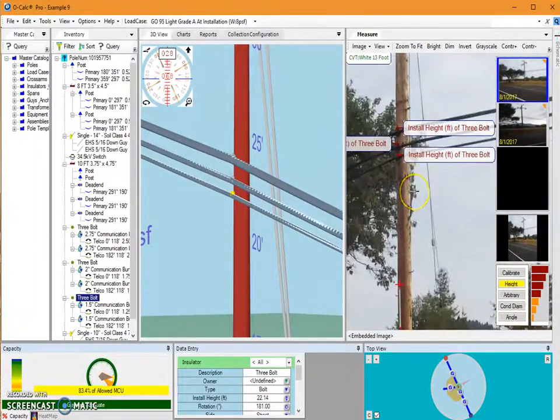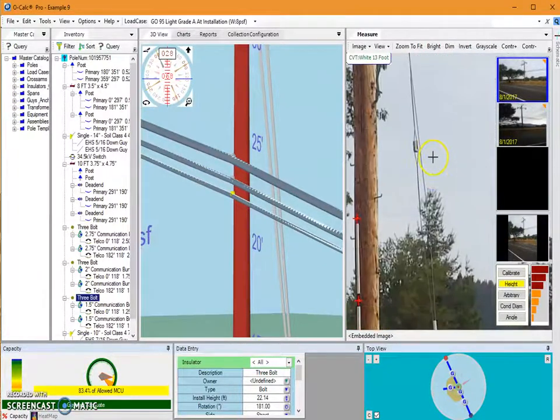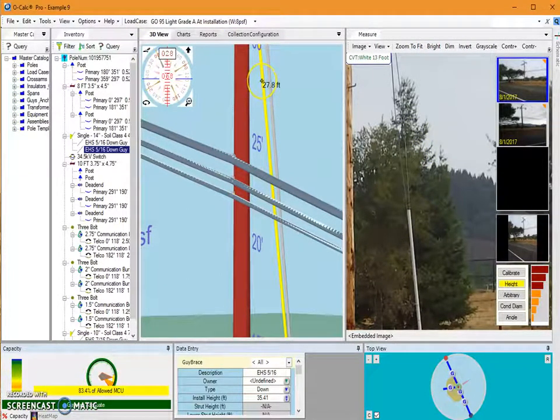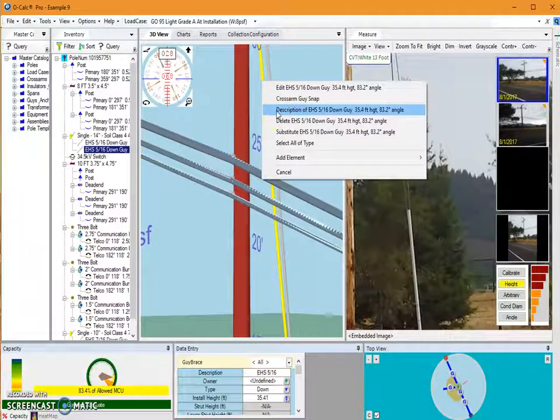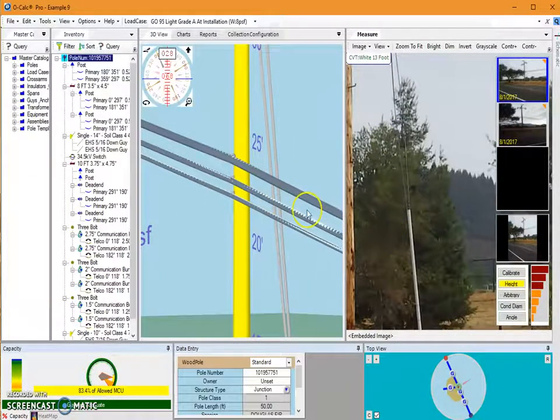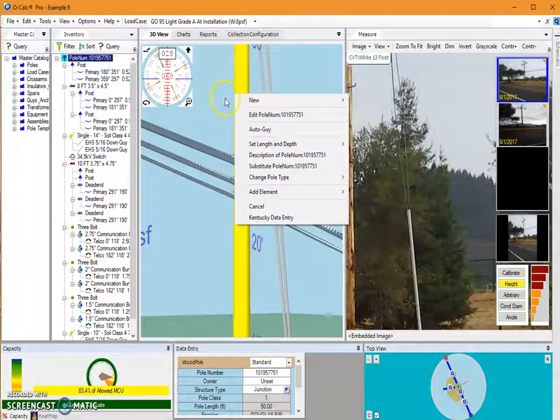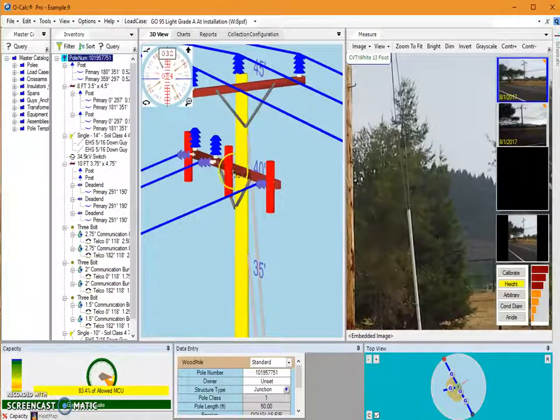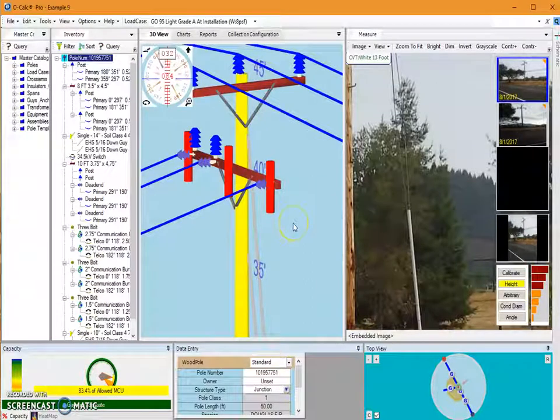Moving down the pole, it looks as though there may be two guy wires here, but they both go into one — so I actually have an extra guy wire in my 3D view. I could delete it, but that would likely overload the pole, so that's something to check in the field. For the purposes of using our CVT tool we can leave everything alone. For items like transformers or streetlights, you would approximate the midpoint between the top and bottom of the transformer, or where the streetlight is attached. In the coming OCALC 5.03, you'll be able to tell OCALC where that attachment height measurement is coming from — whether it's the top, bottom, or midpoint of the transformer.